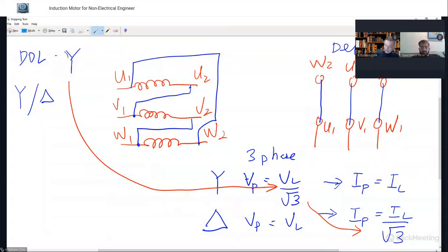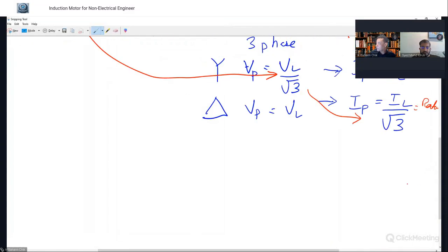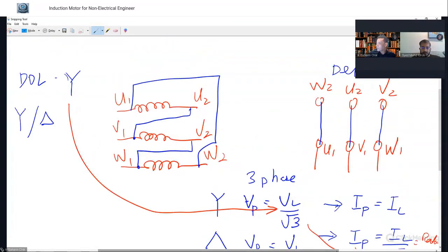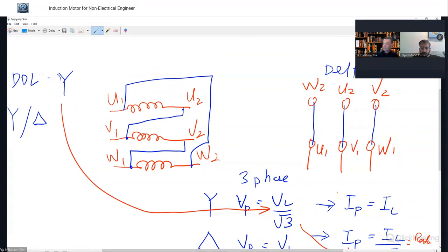Okay, so that is why in some cases to start the motor we use star delta connection. This is to take the advantage of having lower voltage during starting. Then when it runs in delta, with lower current. This lower current is actually the rated current. Okay.